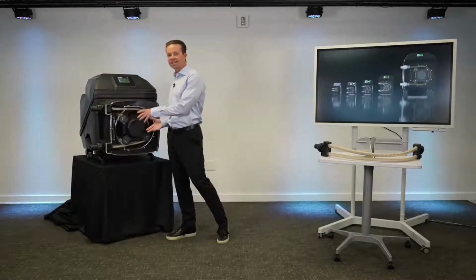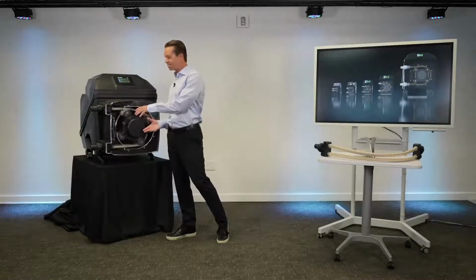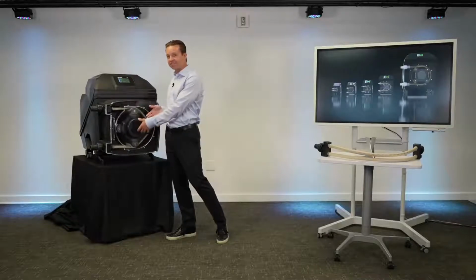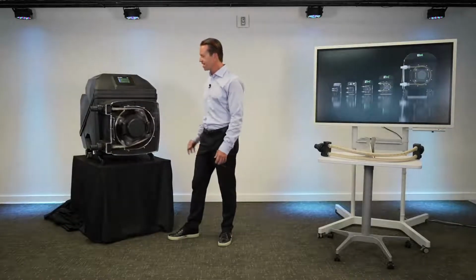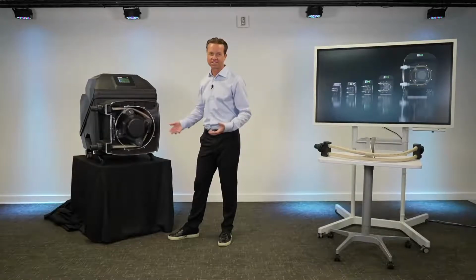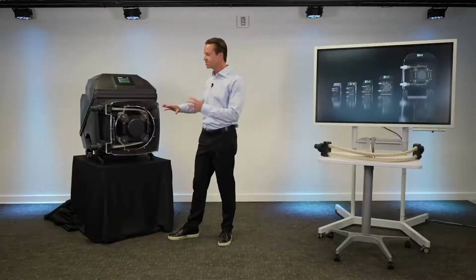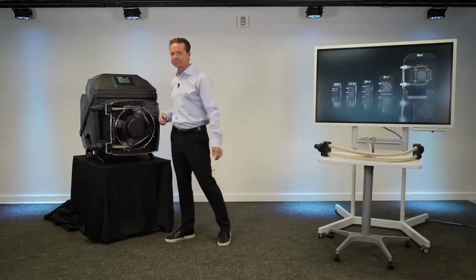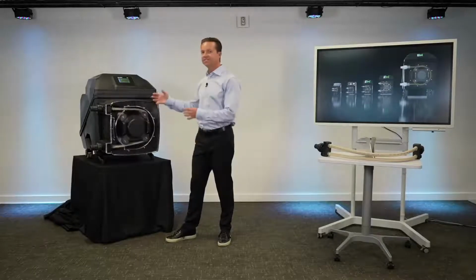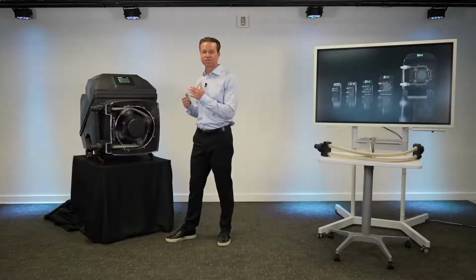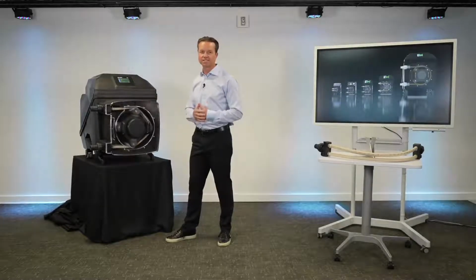On the roller assembly, there's a locking ring. You can unlock it by turning the lock ring to the left, counterclockwise, and it will release the rollers. This is all toolless, by the way. You can slide the rollers out, which relieves the compression the rollers have on the tubing, freeing it up inside the pump.